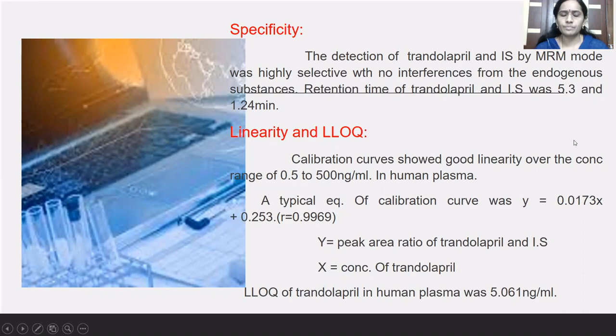Linearity and LLOQ. Calibration curves showed good linearity over the concentration range of 0.5 to 500 nanogram per ml in human plasma. A typical equation of a calibration curve was y equals 0.0173x plus 0.253. Here R is 0.9969, y equals the peak area ratio of trandolapril and internal standard, and x equals the concentration of trandolapril. LLOQ of trandolapril in human plasma was 5.061 nanogram per ml. And coming to recovery and matrix effect, extraction recovery was in the range of 85.0 to 115, and no matrix effect was observed for the analyte.